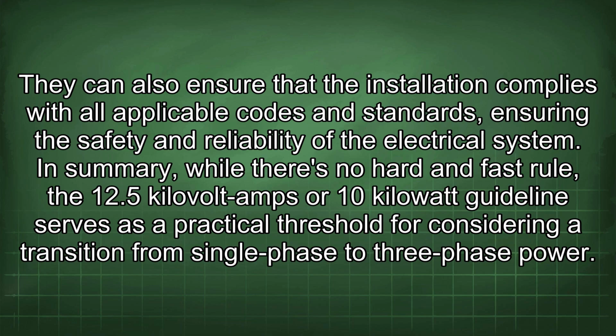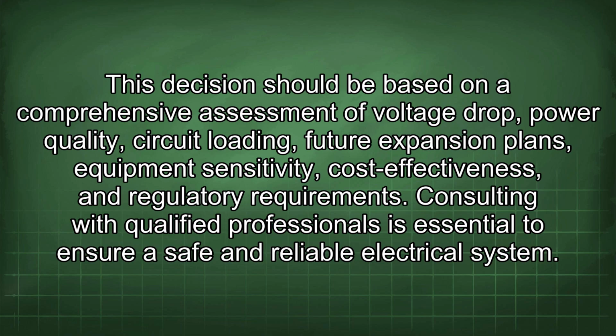In summary, while there's no hard and fast rule, the 12.5 kilovolt-amps or 10 kilowatt guideline serves as a practical threshold for considering a transition from single-phase to three-phase power. This decision should be based on a comprehensive assessment of voltage drop, power quality, circuit loading, future expansion plans, equipment sensitivity, cost effectiveness, and regulatory requirements. Consulting with qualified professionals is essential to ensure a safe and reliable electrical system.